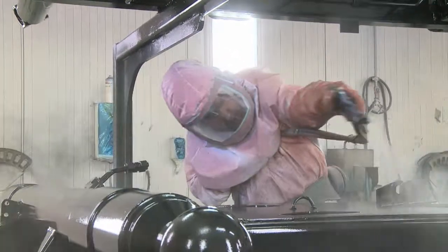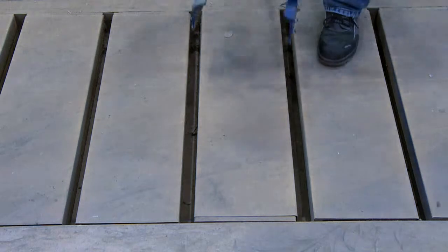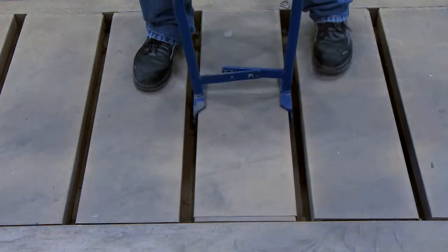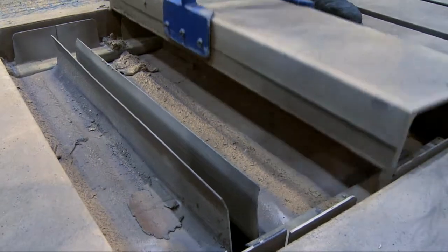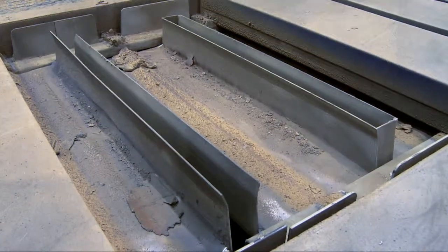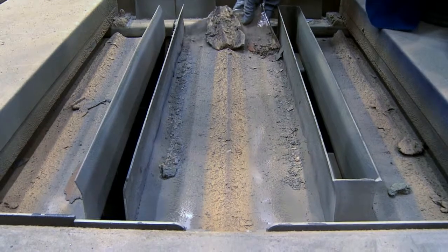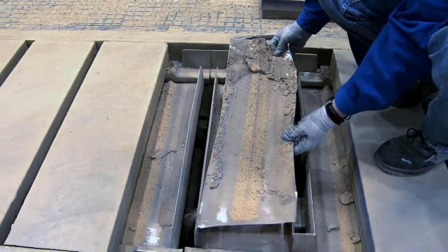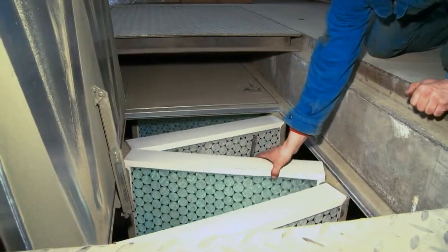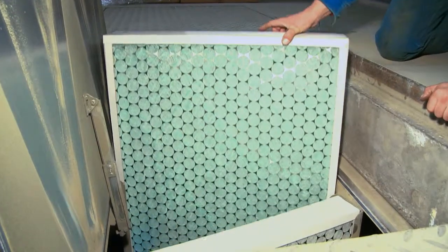The extraction system in these cabins uses a 2-stage filtration process based on impact collectors and downstream cassette filters. The air guidance system of the impact separators causes a very significant percentage of the particulates to collect on an easy-to-exchange aluminium foil. Only a small amount of remaining suspended material needs to be captured by the filter mats.